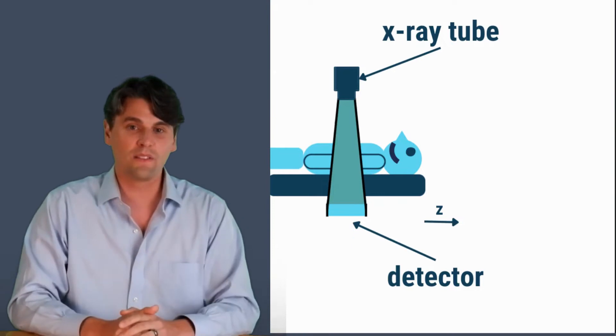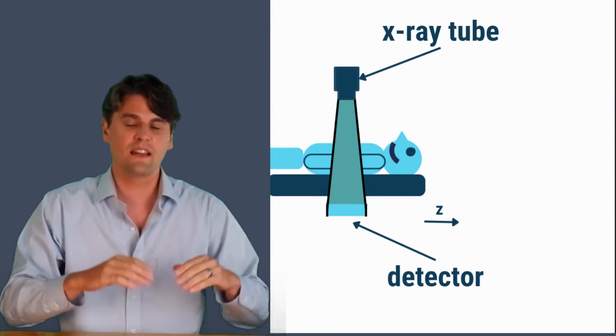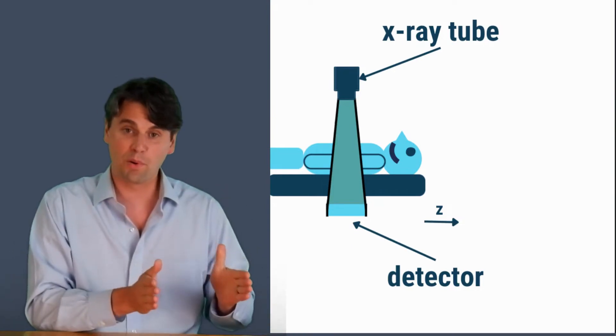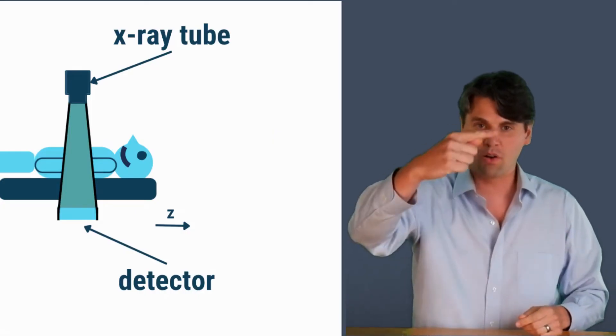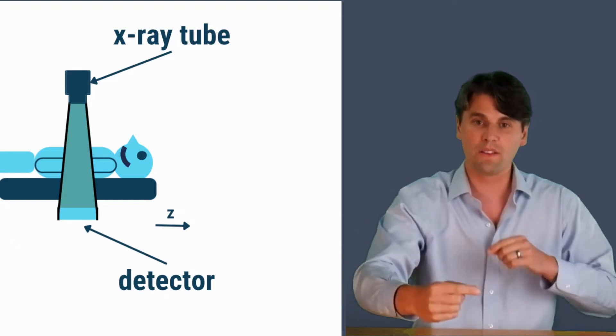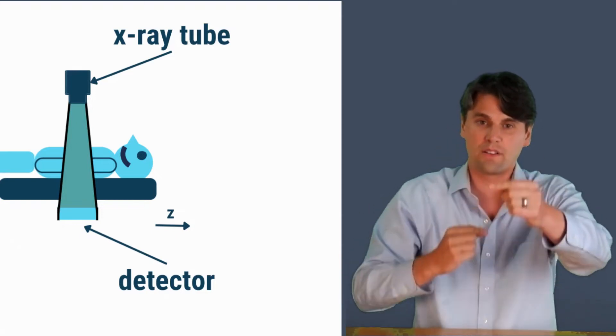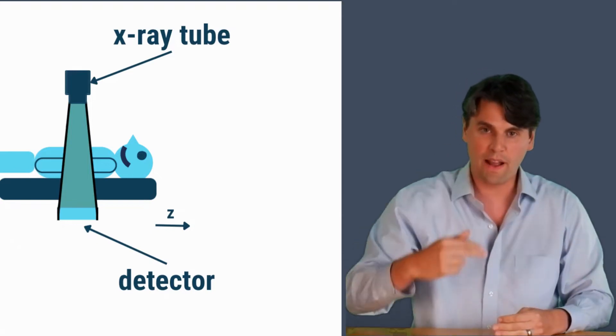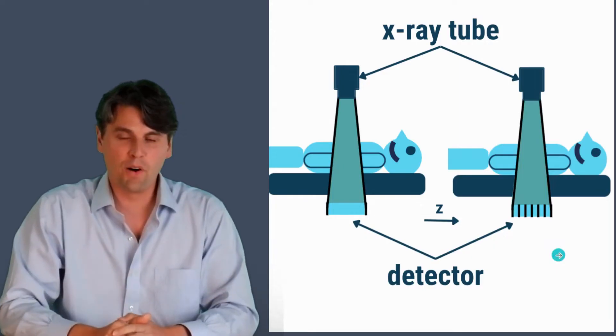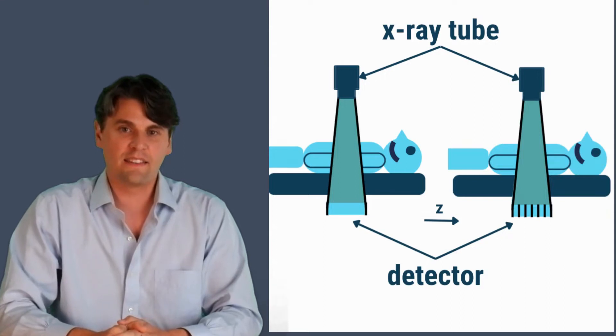This is the old days of single slice CT. Often the slices would be pretty thick in that direction, so in axial scanning the x-ray tube would go around and the detector would go around. They're always facing one another, 180 degrees apart. To make one image you go around one rotation. Multi-slice CT is actually the idea that you could take that same width in the detector...